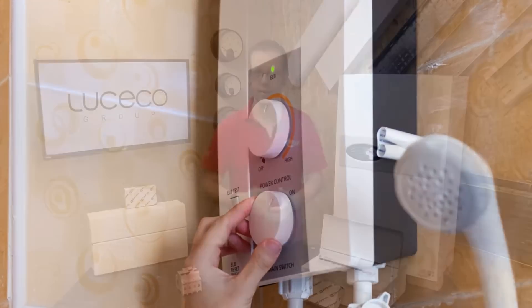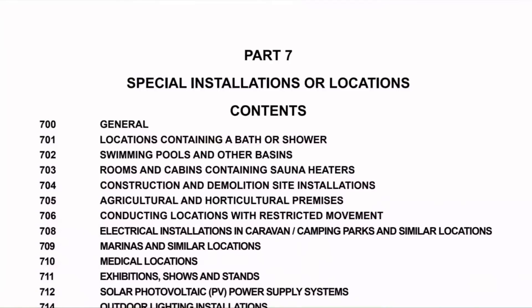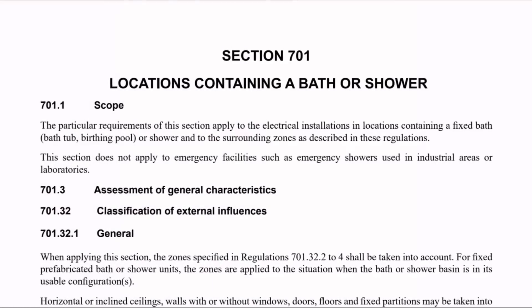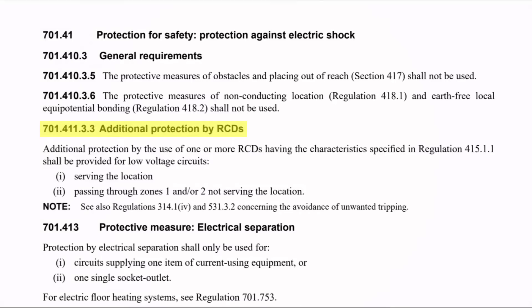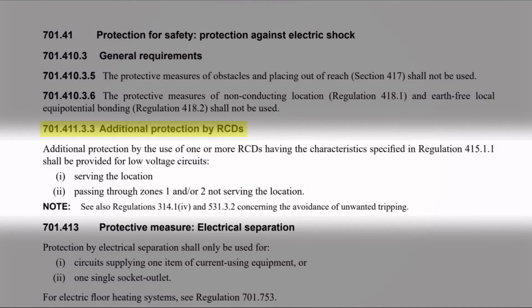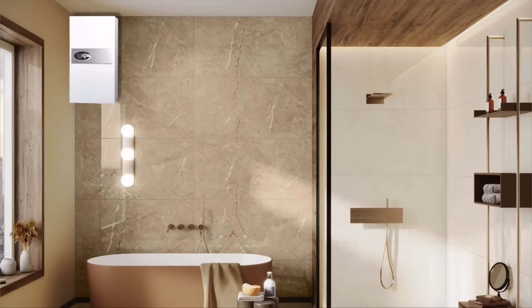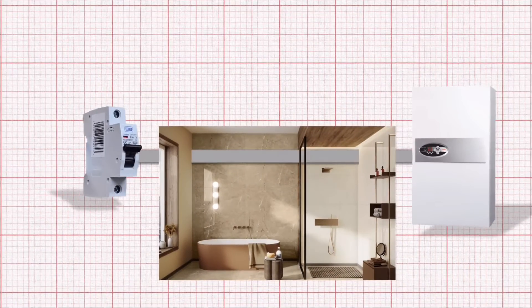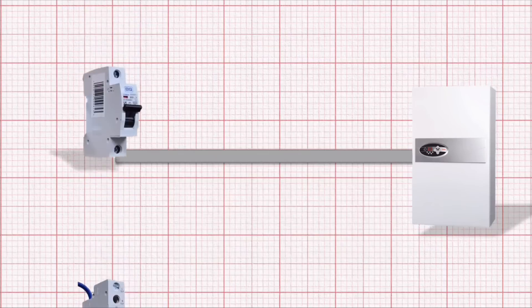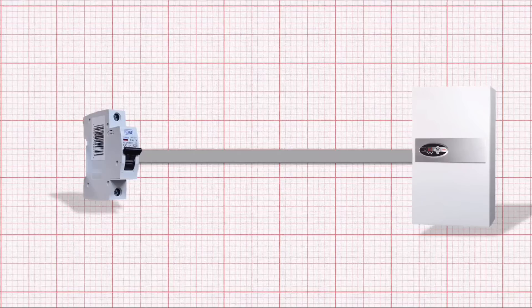We may feel inclined to use one because if we supply an electric shower in a bathroom, there is clear direction to protect that with an RCD. We find that in Part 7 on special locations, specifically Chapter 701 - all about bathrooms and shower rooms - regulation 701.411.3.3, additional protection by RCDs. This applies to low voltage circuits serving the location, such as an electric shower, or passing through zones 1 and/or 2. There is a fringe but unlikely case where a boiler could be sited in a bathroom, or its cable could pass through zone 1 or 2, which would then require an RCD.